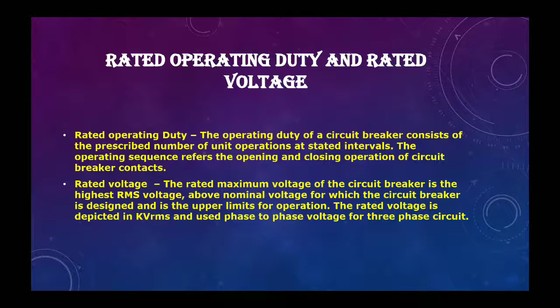And the rated voltage, the rated maximum voltage of circuit breaker, is the highest RMS voltage above nominal voltage for which the circuit breaker is designed as the upper limit of the operation. That means above this voltage, the puncture strength of the circuit breaker insulating materials breaks down. The rated voltage is expressed in kV RMS and uses phase-to-phase voltage for three-phase circuit. So basically that is the line voltage. Phase-to-phase voltage means the line voltage for a three-phase 3-wire line or three-phase 4-wire line. So that is the rated voltage.